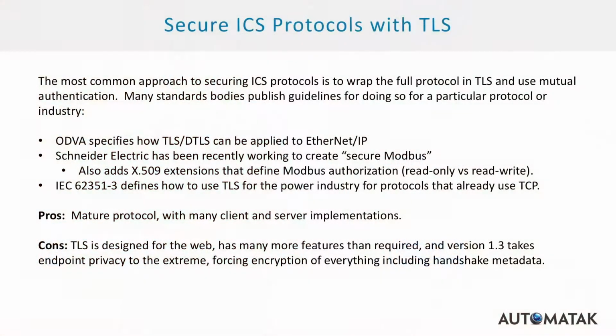Schneider Electric has been pushing a secure version of Modbus that says here's how you secure Modbus. It goes a little bit beyond that because they're embedding access control lists in the certificates, which is kind of neat. This person with this certificate should only be able to perform write access to the device. In the electric power industry, we have a standard from the IEC that basically says here's how you apply TLS to protocols in the electric power industry.